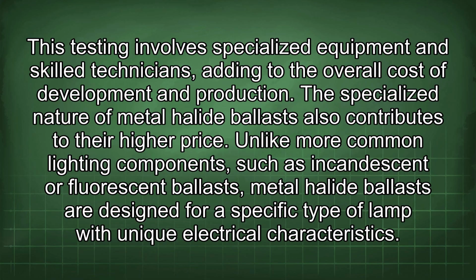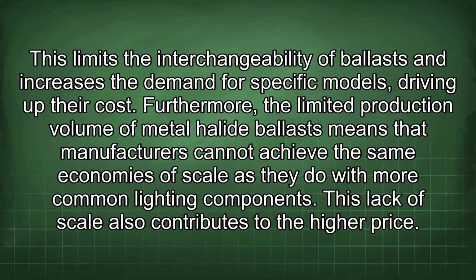The specialized nature of metal halide ballasts also contributes to their higher price. Unlike more common lighting components, such as incandescent or fluorescent ballasts, metal halide ballasts are designed for a specific type of lamp with unique electrical characteristics. This limits the interchangeability of ballasts and increases the demand for specific models, driving up their cost. Furthermore, the limited production volume of metal halide ballasts means that manufacturers cannot achieve the same economies of scale as they do with more common lighting components. This lack of scale also contributes to the higher price.